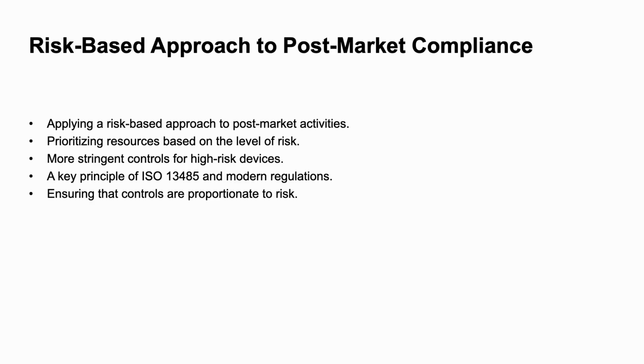of post-market compliance. The principle states that a manufacturer should prioritize its resources and controls based on the level of risk associated with a device. For example, a manufacturer should apply more stringent post-market controls to a high-risk implantable device, like a cardiac pacemaker, than to a low-risk bandage. This approach ensures that a company's resources are focused on the areas that have the greatest impact on patient safety. It is a fundamental shift from a one-size-fits-all approach to a more intelligent, risk-based approach to quality management. An auditor will expect to see evidence of this risk-based approach throughout the QMS, from the initial design and development to the post-market phase.